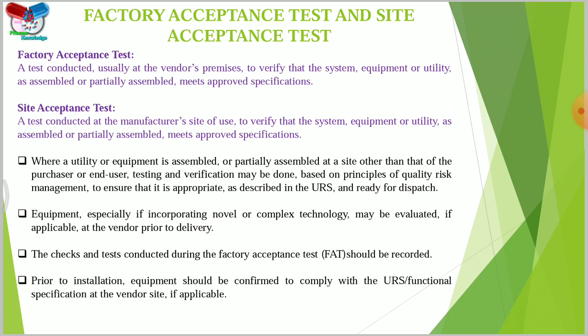Now the next detail about the factory acceptance and site acceptance test. Where appropriate and justified, documentation review and some tests could be performed at the FAT or other stage without the need to repeat a site IQ, OQ, if it can be shown the functionality is not affected by the transportation and installation. It means if you have performed some tests during FAT and SAT, then you can club these tests with IQ and OQ when there is no impact on the equipment due to transportation and installation.